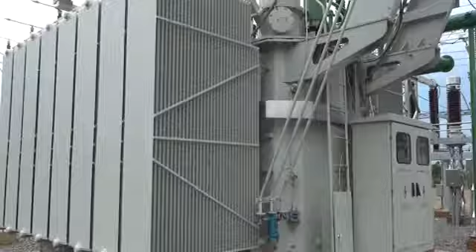He said the station was commissioned in 1980 with a 30 MVA transformer, but was later upgraded to 60 MVA. When studies showed the city is expanding due to various institutions and industries, it was decided to increase the station by another 60 MVA capacity. With the substation capacity upgraded to 120 MVA, bulk power supply to Abuja Electricity Distribution Company, AEDC, has increased, improving electricity available for distribution to households in Bida Town, Lemu, Zungeru, Army Barracks, Dogo, Agaye, Kacha, and Kutugi, through AEDC's injection substation connected to the Bida transmission substation.